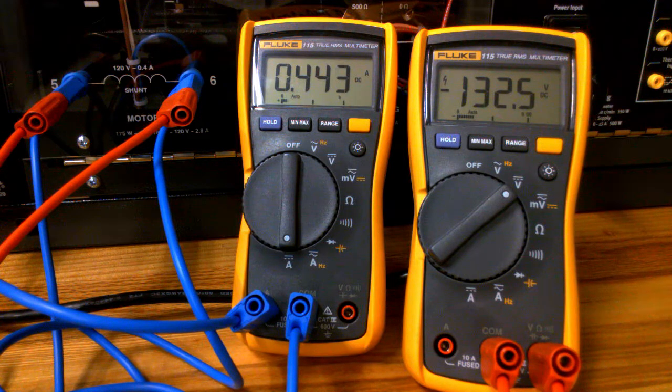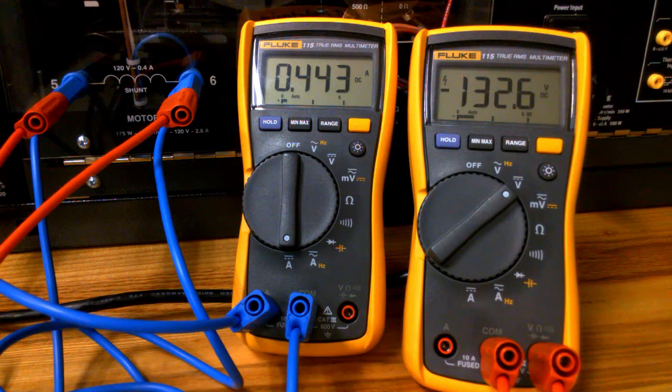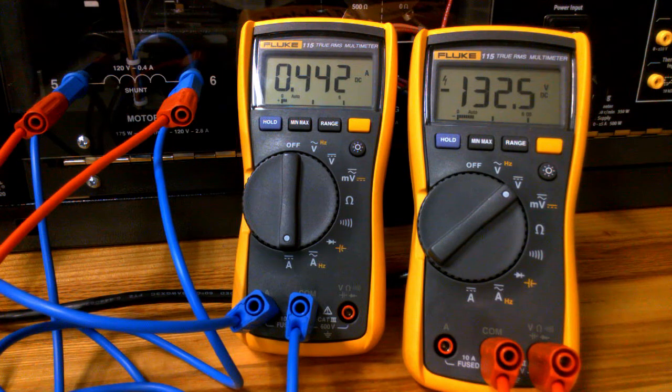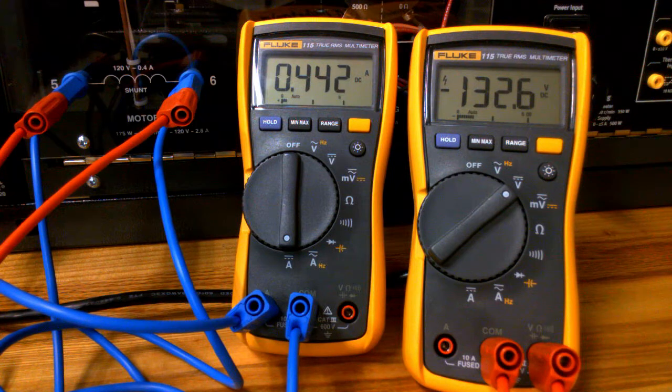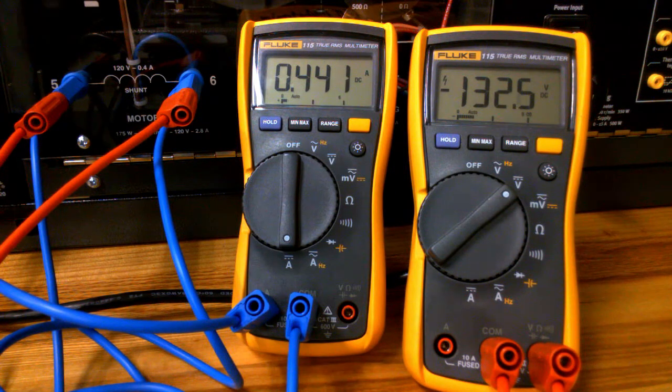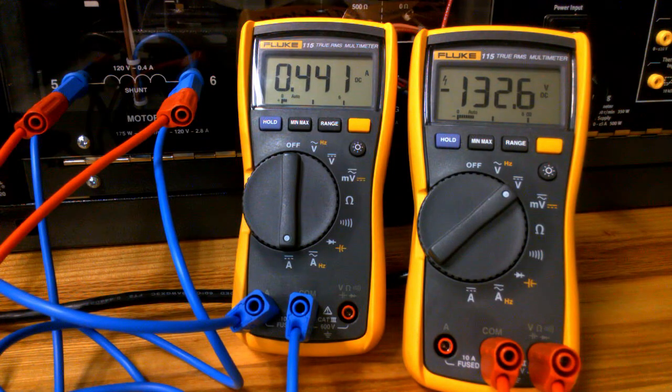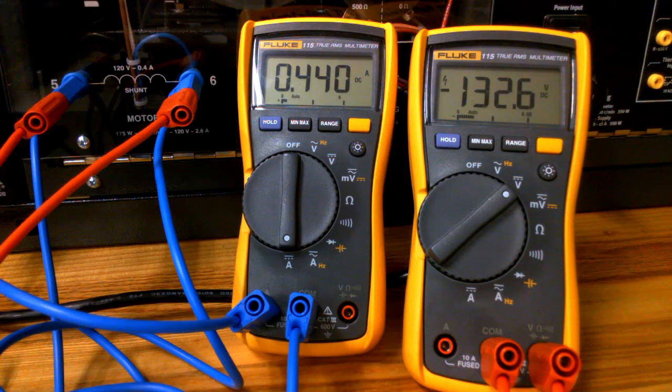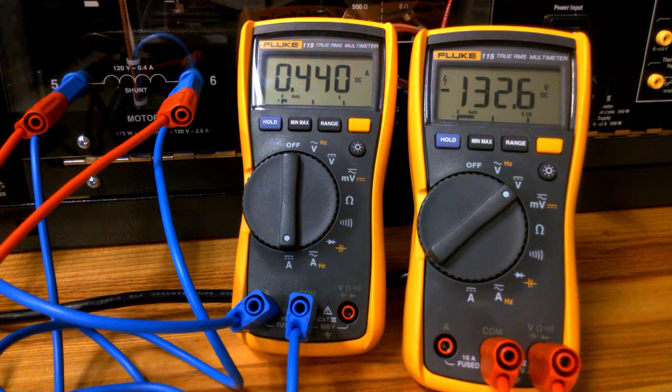Current meter in series, voltmeter in parallel. Power on. I show that a direct reading across the winding shows 132.6 volts applied, and we have 0.442 amperes flowing in the field circuit.